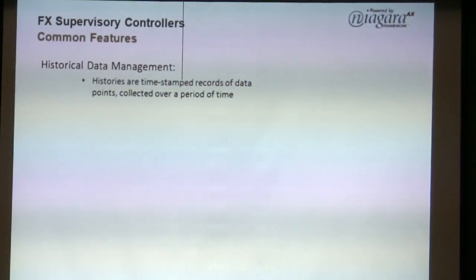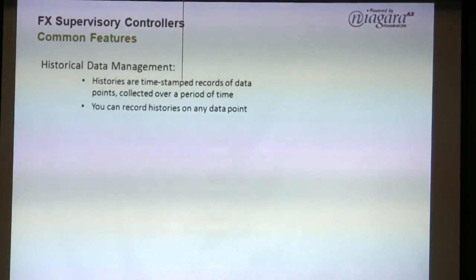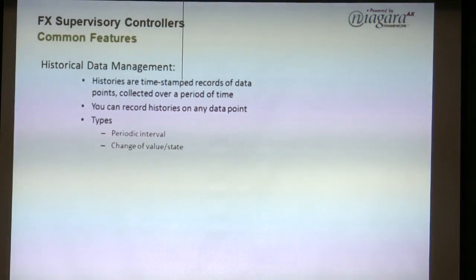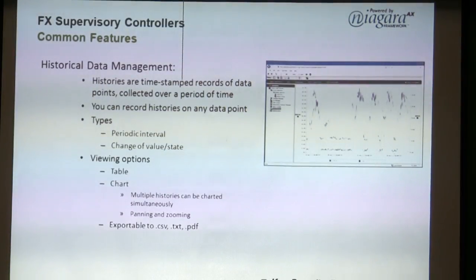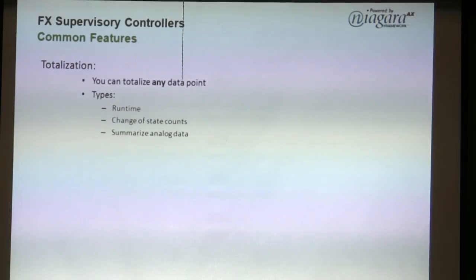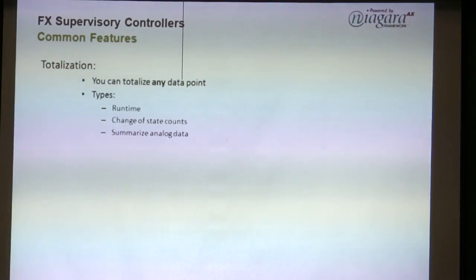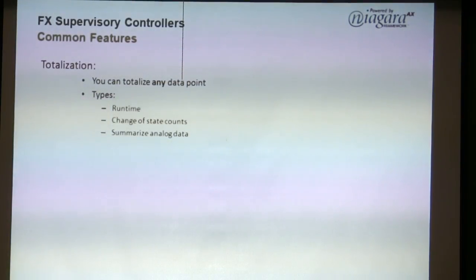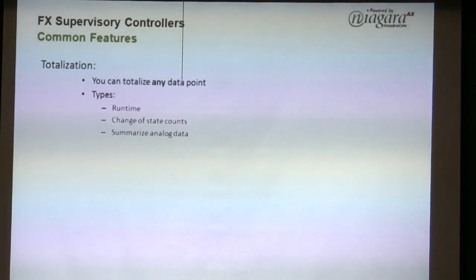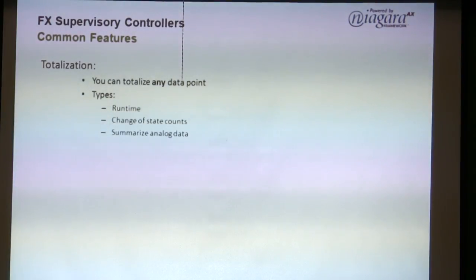Historical data management covers all your trending and reports. Totalization is useful — for example, if you have two Modbus pumps doing lead-lag, you can track runtime on each one. So if the last one wore out at a certain point, you can use that data for budgeting and plan maintenance on the current one proactively.